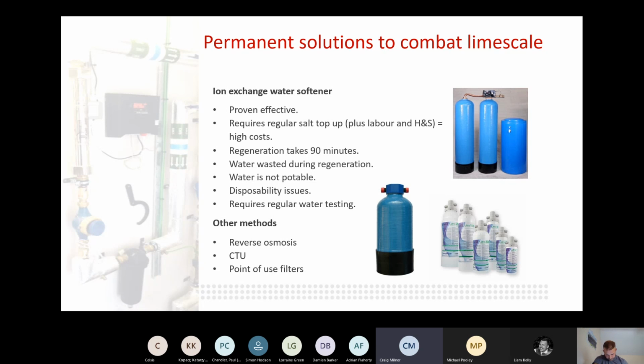Unless you blend it back, it's not classed as potable. The other thing is it's actually on the HSE list of risk factors for Legionella. So if the resin bed isn't cleaned out or doesn't get a good enough flow, with low flow it can become a bacteria trap. So it is listed as a risk factor under the Legionella HSE document.